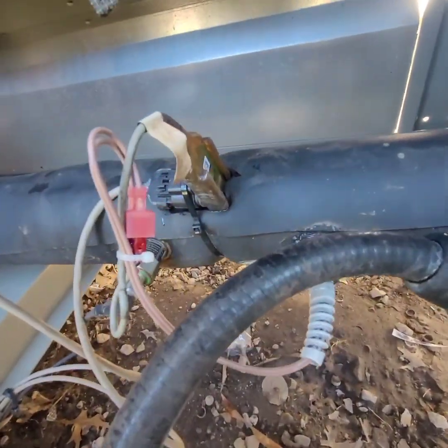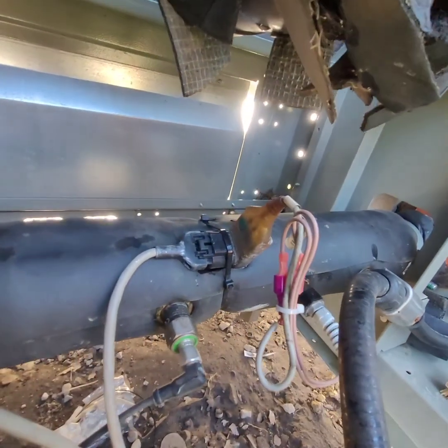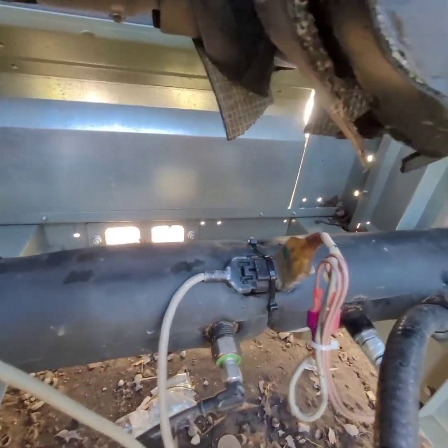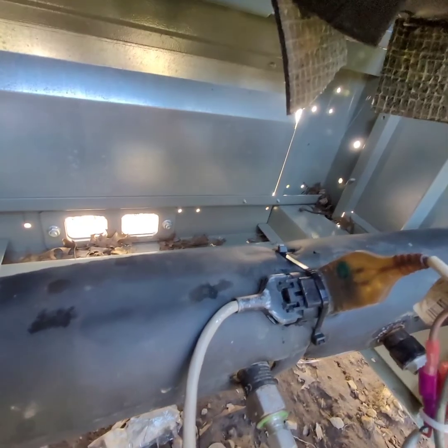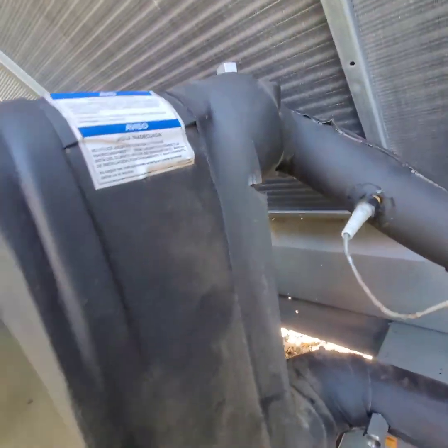Alright, I have that new sensor in. Leaving water temperature sensor. This chiller wouldn't run before. It is a temporary one. I didn't replace the module. That's the original there. That's the one I put in. It's running well.